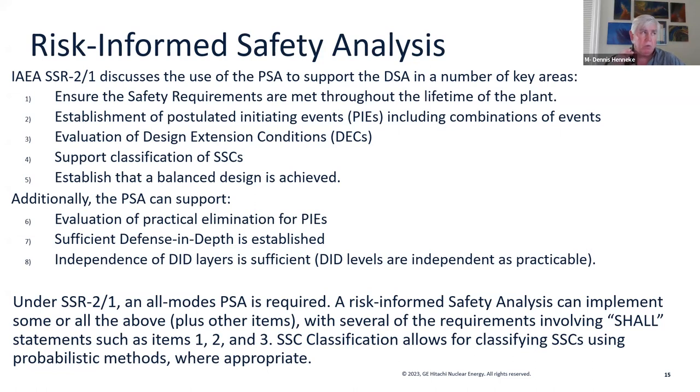You can see if you read SSR 2-1 that the risk-informed safety analysis that they require in the series of shall statements has a number of things that you can do. Establish the safety requirements, ensure they're met through the lifetime of the plant, establish the postulated initiating events, evaluation of the design extension conditions as well as the DSA, safety classification, ensure the design is balanced. That's an interesting one, which we could talk about separately if anybody wants to. Additionally, the PSA can be used in the evaluation of practical elimination for postulated initiating events, if you want to put together an argument for that, so that it doesn't have to be a part of your safety case, whether you have sufficient defense in depth, and whether the layers of defense in depth are sufficiently independent.